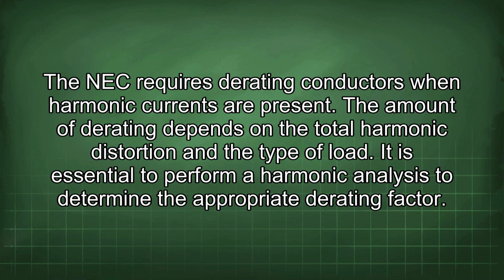The amount of derating depends on the total harmonic distortion and the type of load. It is essential to perform a harmonic analysis to determine the appropriate derating factor.